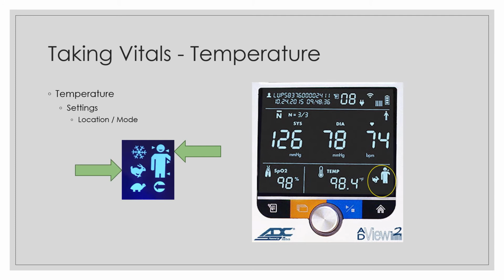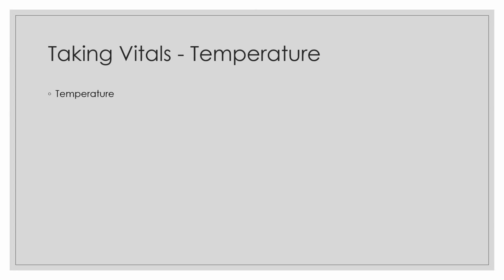The probe is computer controlled to anticipate a typical environment and to obtain a ready, quick, usually within 15 seconds, temperature. Quick mode is indicated with the rabbit or bunny and with the arrow pointed to the patient's head or oral. We will discuss other modes such as cold and direct modes later in this session. When the uncovered probe is holstered, the unit is in standby mode.